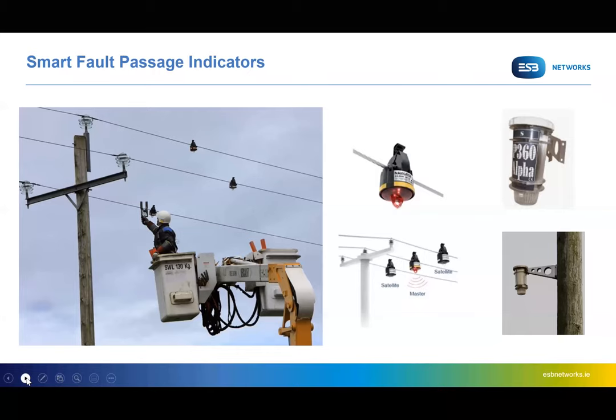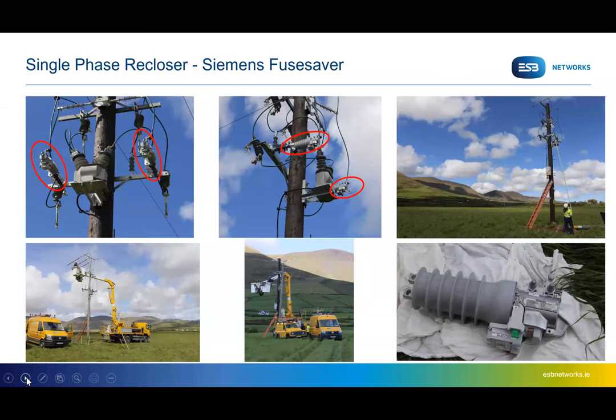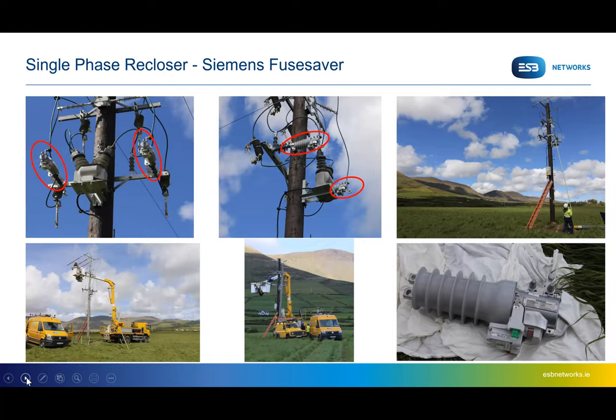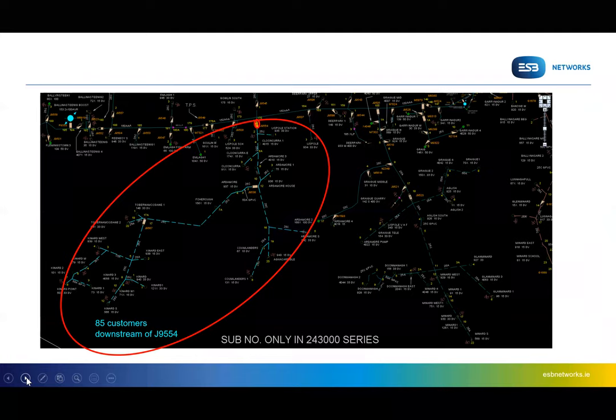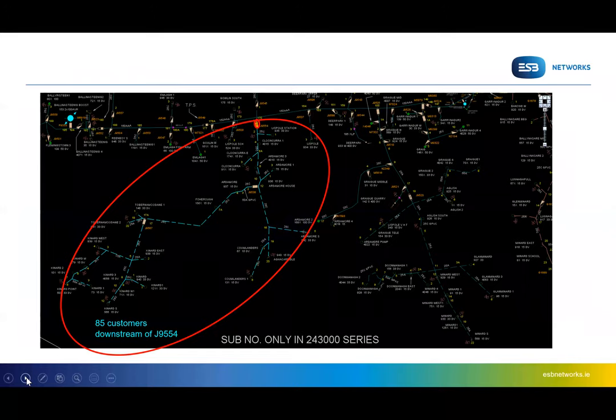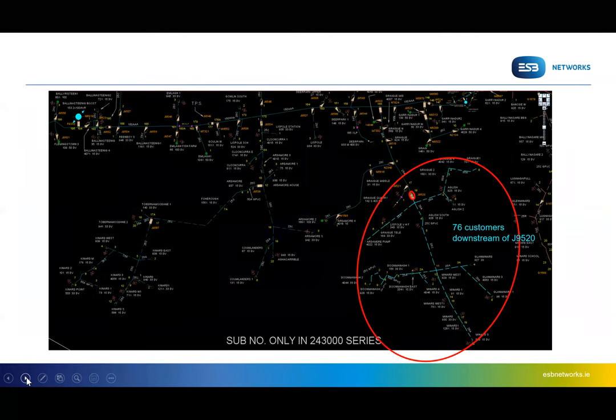I suppose this slide here now is just a few photos of the installation of the single phase reclosers at two of the locations on the network. And I suppose the key thing about this is for one of those single phase reclosers, there are potentially 85 customers downstream of it who would benefit if there was a transient fault on the network. And for the other one, there's 76 customers downstream.